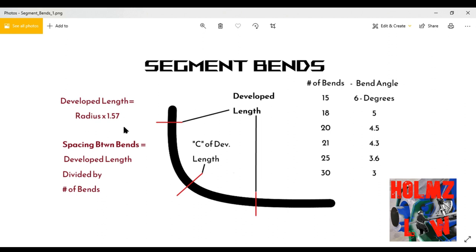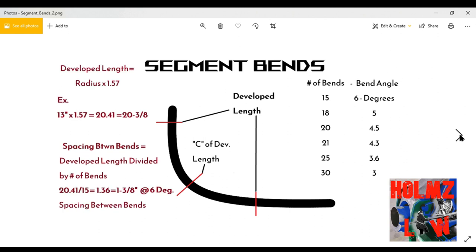Once you decide on the number of bends and what degree works for you — or vice versa, pick the degree first and determine the number of bends — you need to enter it into the formula. Take the developed length and divide it by the number of bends. That gives you your spacing between bends, and that's it for that portion.